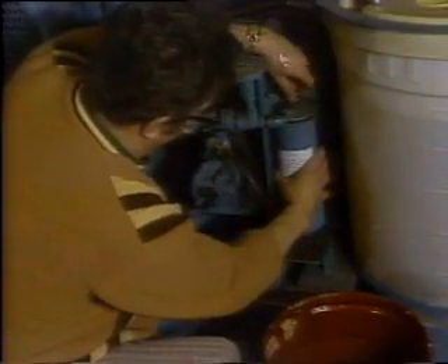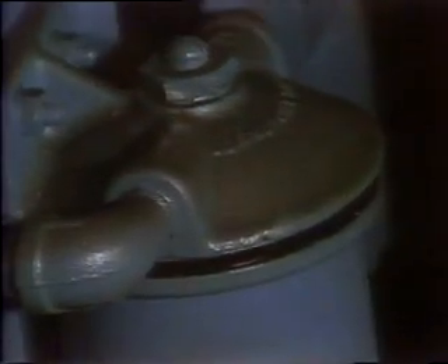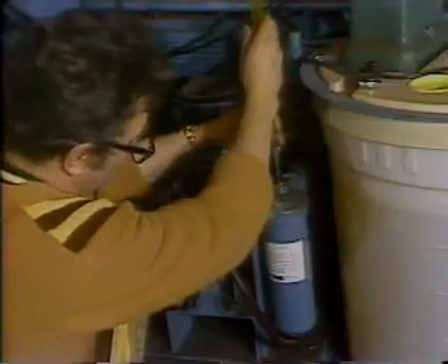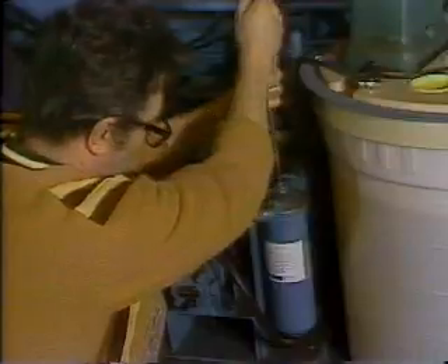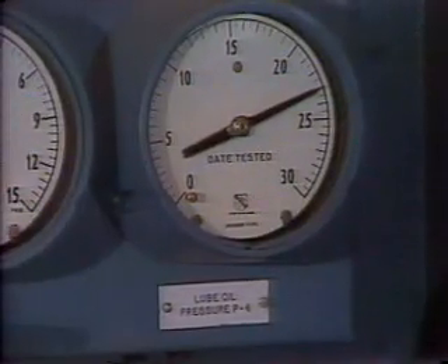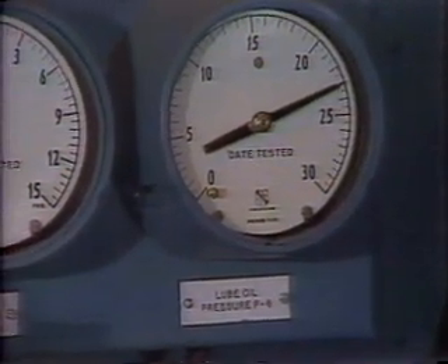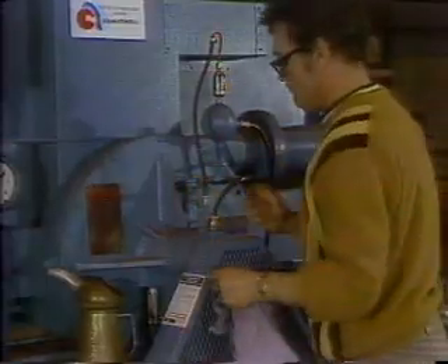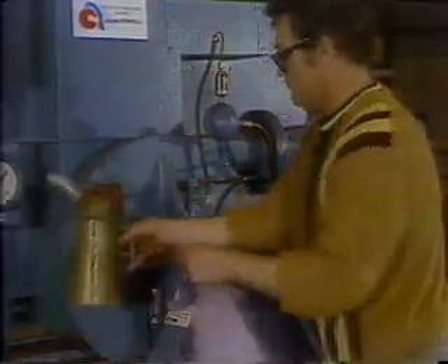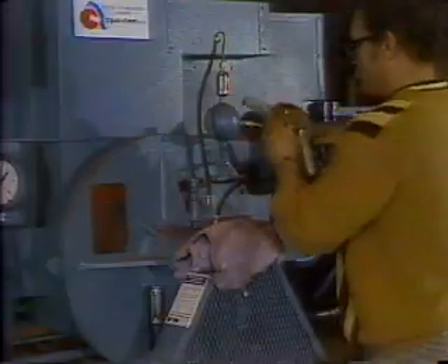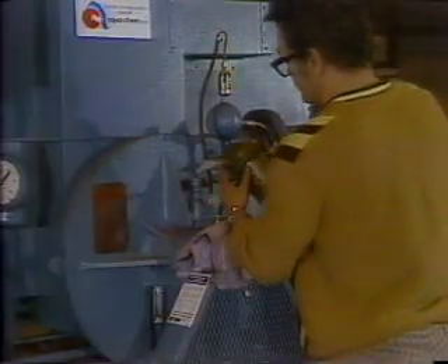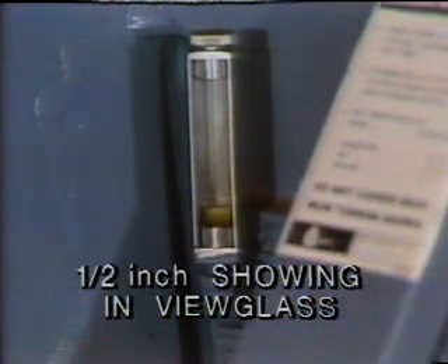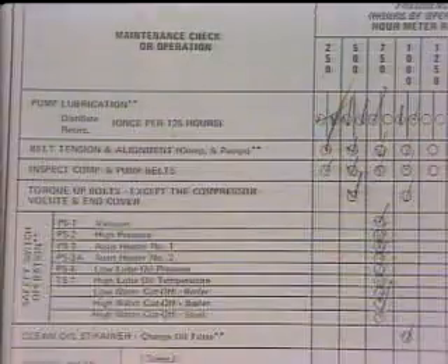Tighten the hex nut first, preferably with the right-sized wrench instead of pliers. Then use a screwdriver to tighten the screw. Turn the lube oil pump on and let the pressure rise. Remove the breather cap and add oil. Keep adding until there's about a ½ inch showing in the view glass.